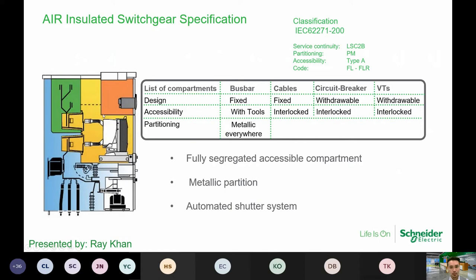All right, so there's the table here, and you can see that it is withdrawable. What it does is that you can withdraw the circuit breaker to a safe location, and then you can do your maintenance. The orange portion is the low voltage compartment at the top. All right, and then the blue compartment here is the cable entry compartment. Now, air insulated switchgear comes with a very distinctive design, which is the automatic shutters. These are shutter systems. What they do is that when you draw out the circuit breaker, the shutter automatically closes itself.